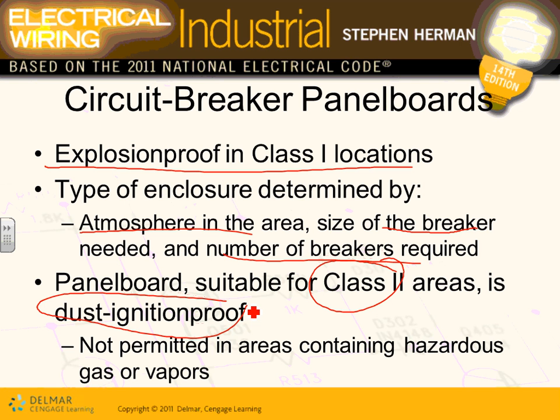You know what the manufacturers of this equipment will do, Derek? They have one piece of equipment because they don't want to split hair. On the equipment, they say Class 1, Class 2, Class 3, Div 1 and Div 2, and they list all the gases and the vapors and say, here, run with it. So that's how they do it, guys. They use one product that can meet all these requirements. Now, if you want to split hair and buy cheaper equipment, there are other manufacturers who can give you dust-ignitionproof equipment. That's it. I don't want explosion-proof, so it will be cheaper equipment.